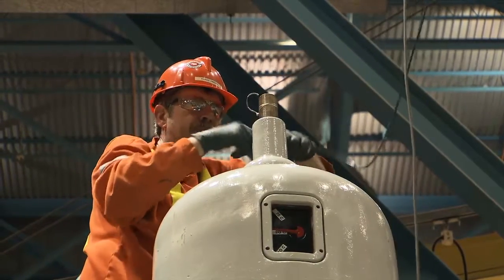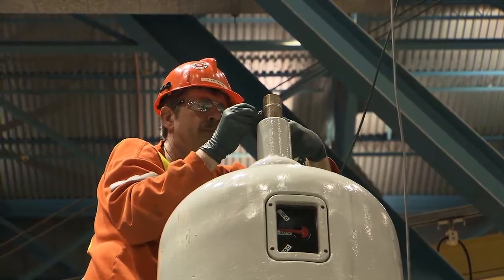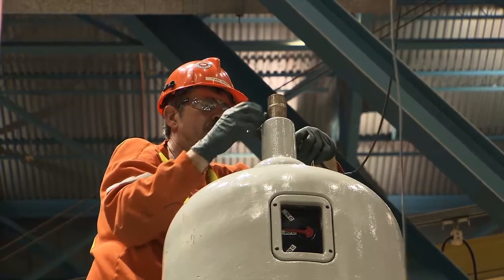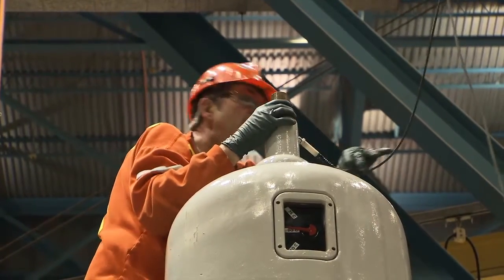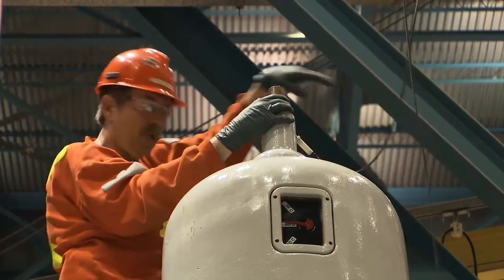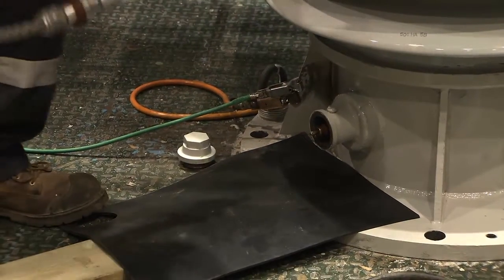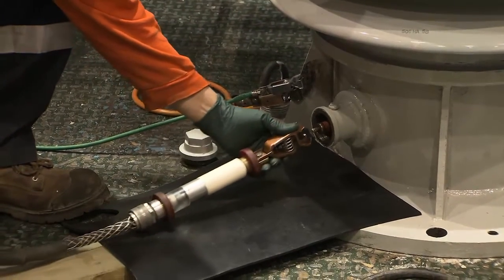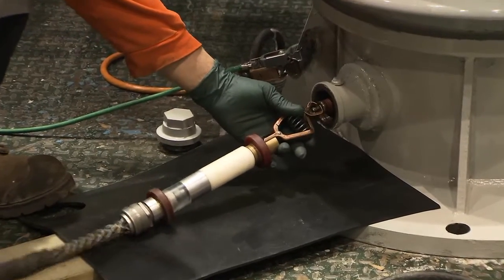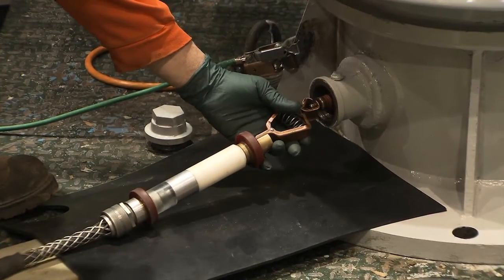And connect the strand of bare copper wire wound around the threaded rod at the top of the terminal. Connect the high voltage lead to the capacitance tap and rest the cable on the rubber mat and the block of wood on the floor below. There you go.